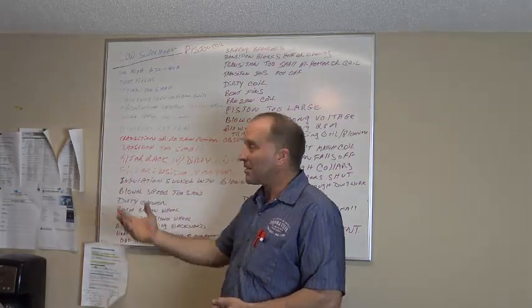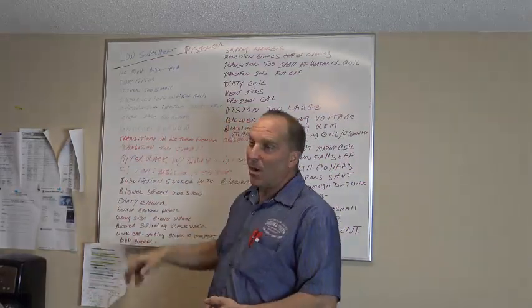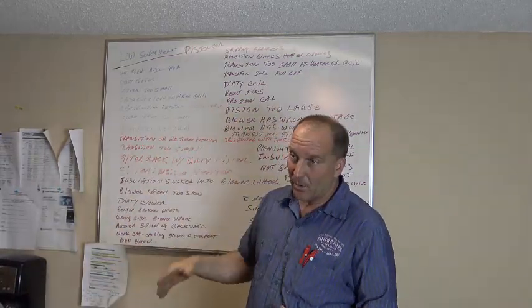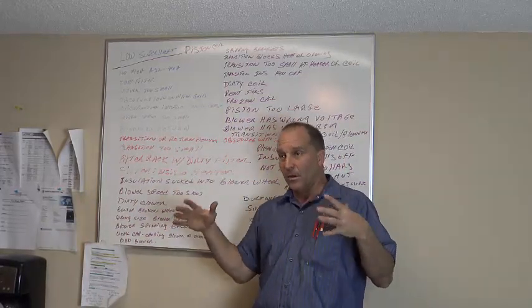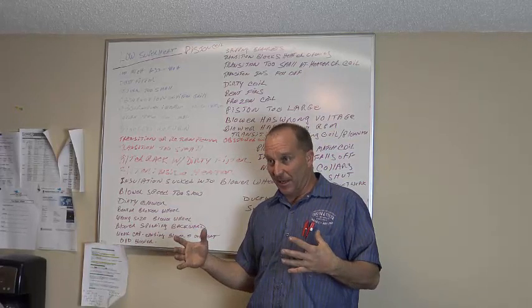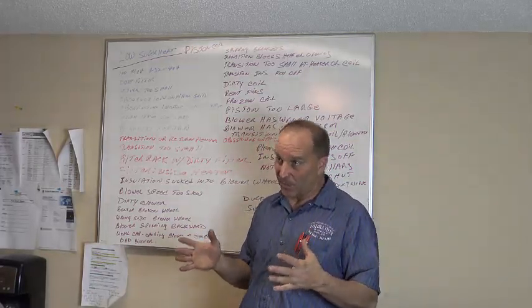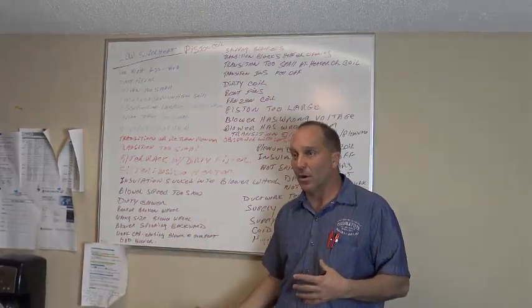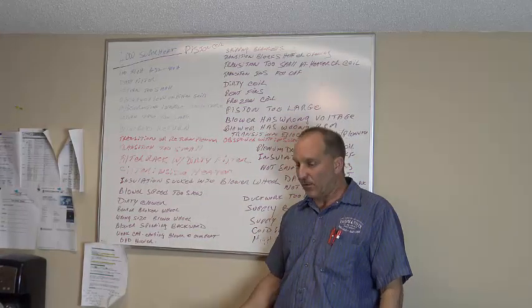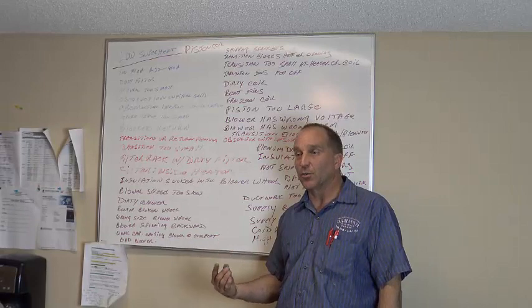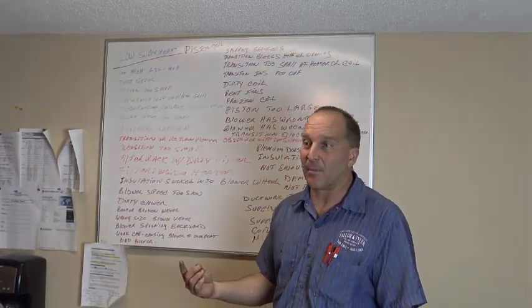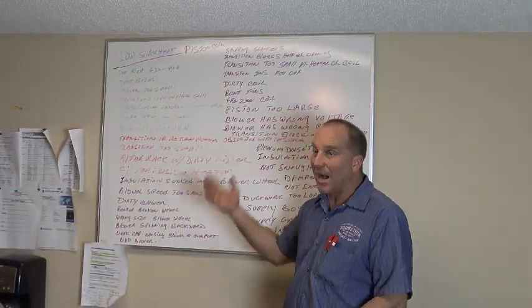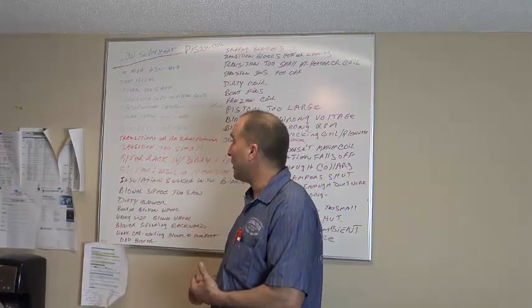You continue to go past that, and your return chase is too small. So you may look into the top plate, and there may be a 2x8 or a piece of 2x2 plywood blocking off half of the return chase, and a little bitty small plenum at the very top of that chase blocking it off. We've seen it a dozen times. So don't assume that when you stick your head in that return air that everything's going to be fine from the floor all the way to the top. A lot of times it's restricted, or sometimes you can actually see in the attic up there that the return plenum is not as big as the return chase is. Okay, and that will get into a high superheat on that part. Here we're working on low superheat.